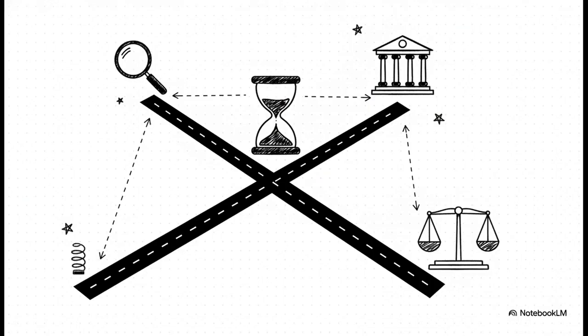Now, what's really interesting here is the totally divergent regulatory paths for that exact same spring change. Over in the US, you're assessing reportability to the FDA under those Part 4 guidelines. But in Europe, a change to the device part might require your notified body to revisit its Article 117 opinion, which then triggers a whole variation to the marketing authorization application. The thresholds for approval and the timelines differ wildly between the US and the EU. You absolutely need one global tracker to sequence these submissions perfectly, because if you don't, you risk massive supply gaps where you're legally allowed to sell in one market, but not the other.